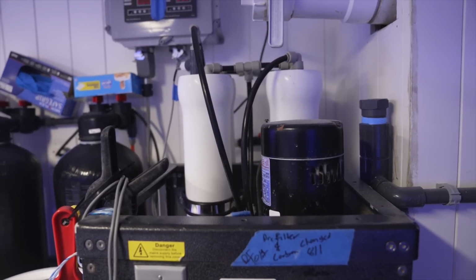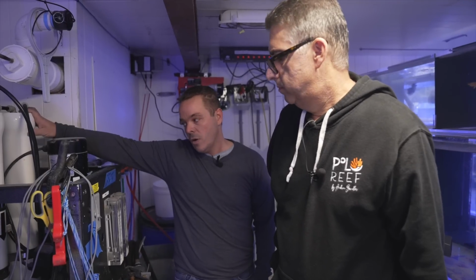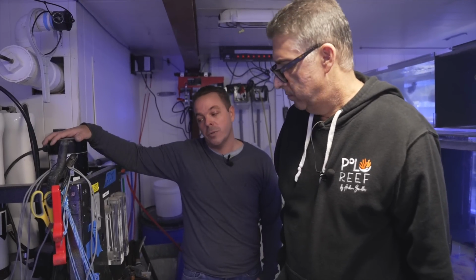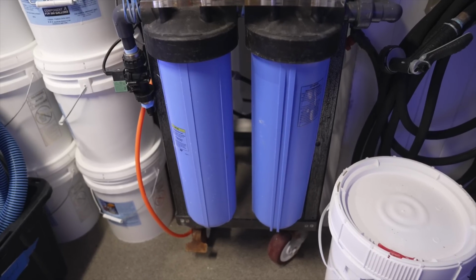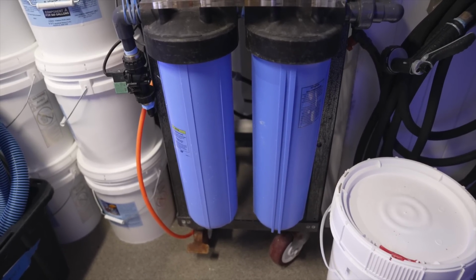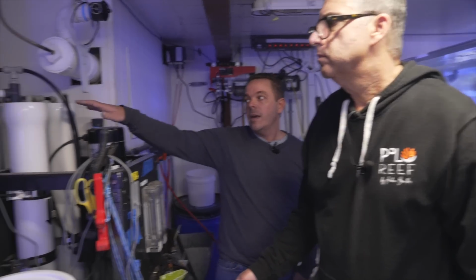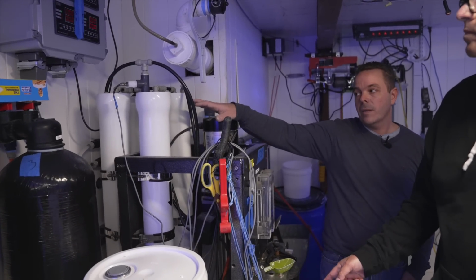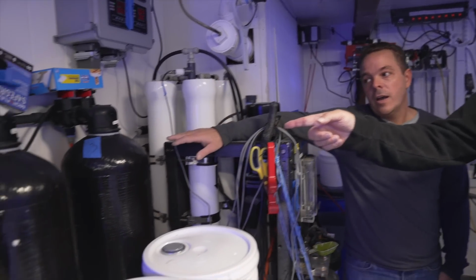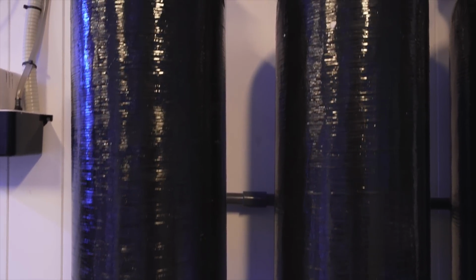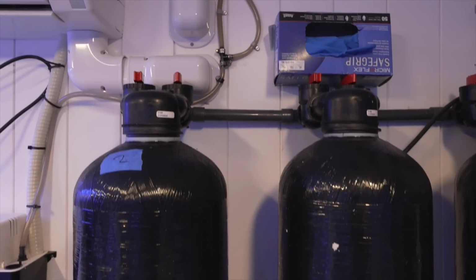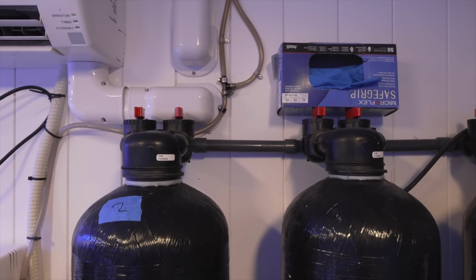It consists of 4.5 inch by 40 inch membranes run by a 1.5 horsepower booster pump. We have a 1 micron pre-filter and a 5 micron carbon block before that. And after the membranes, we then go through a cation, an anion, and a mixed bed DI resin. And these are approximately 10 inches by 60 inches, holding about 100 pounds of DI resin each.